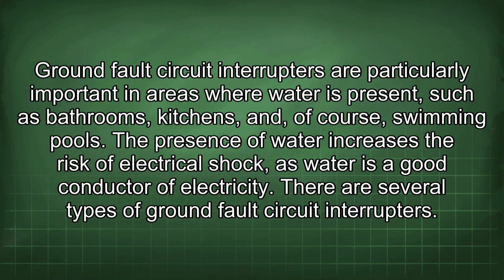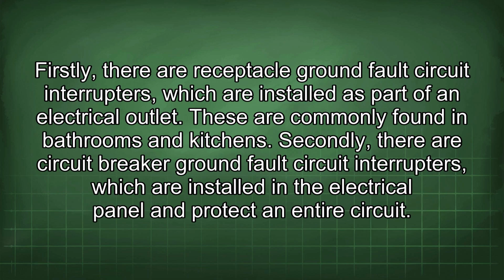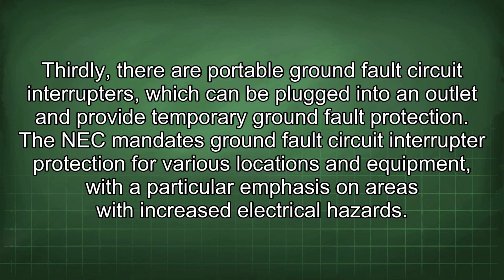The presence of water increases the risk of electrical shock, as water is a good conductor of electricity. There are several types of ground fault circuit interrupters. Firstly, there are receptacle ground fault circuit interrupters, which are installed as part of an electrical outlet. These are commonly found in bathrooms and kitchens. Secondly, there are circuit breaker ground fault circuit interrupters, which are installed in the electrical panel and protect an entire circuit. Thirdly, there are portable ground fault circuit interrupters, which can be plugged into an outlet and provide temporary ground fault protection.